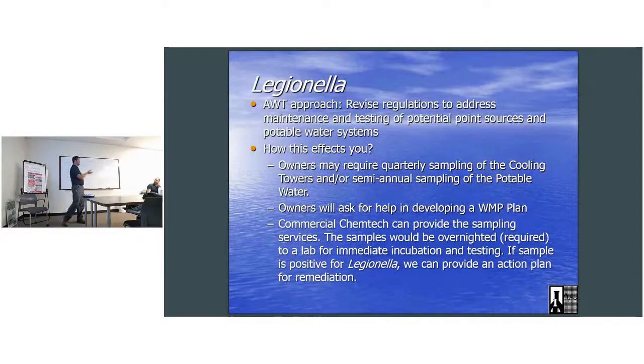And on cooling towers, I always like to grab it specifically from circulating sump water. You can see that on a lot of the controllers, they'll have a little port outlet on it with water circulating. Let it blow out a little bit and then grab a sample from it. Same if you could open up a drift eliminator, grab a sample of the water that's directly circulating in it. Because if you're grabbing particulate off the side of the tower that's growing and then you're shipping it off, it's going to look bad. You want mostly to know if the water that is spraying and spreading is becoming a problem.